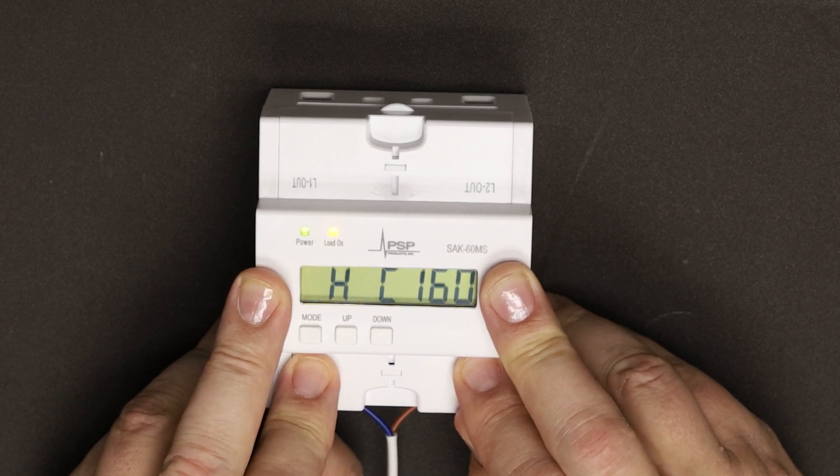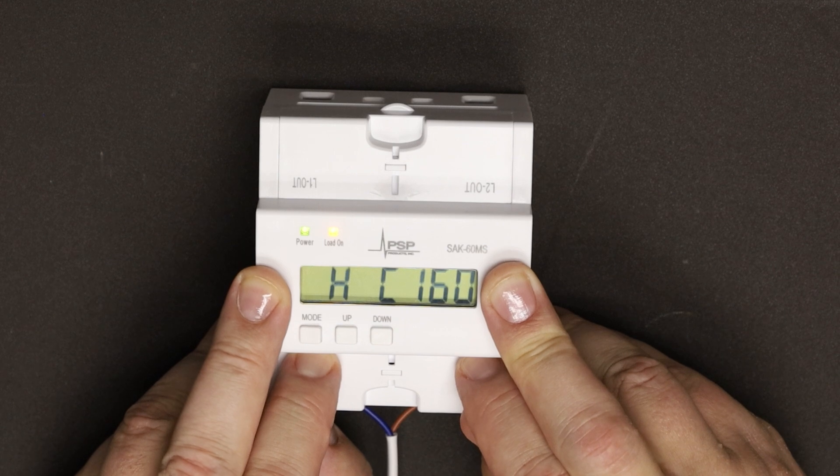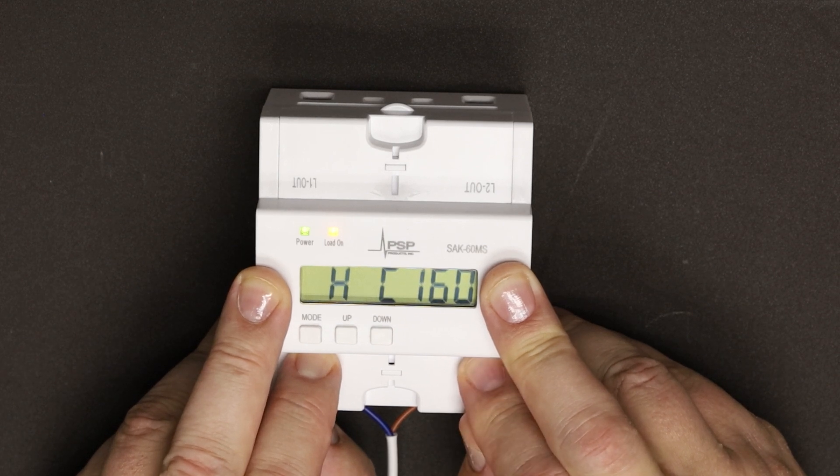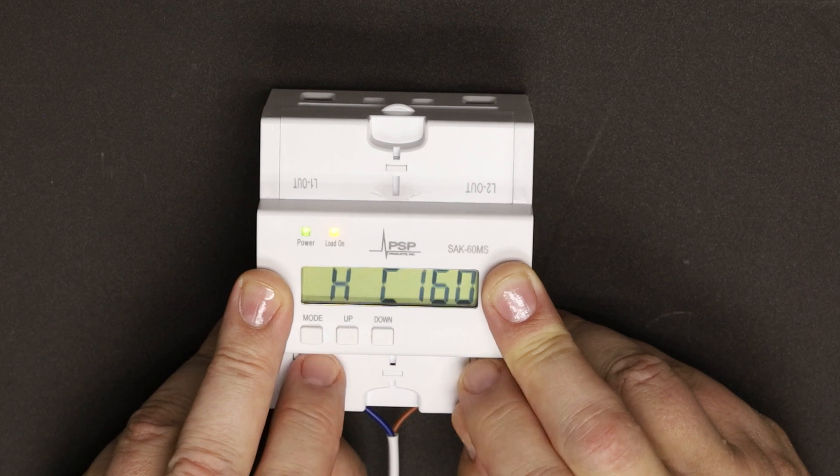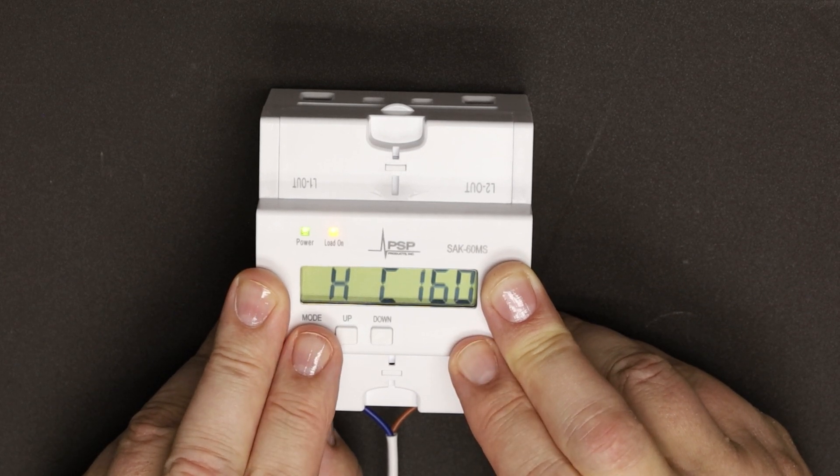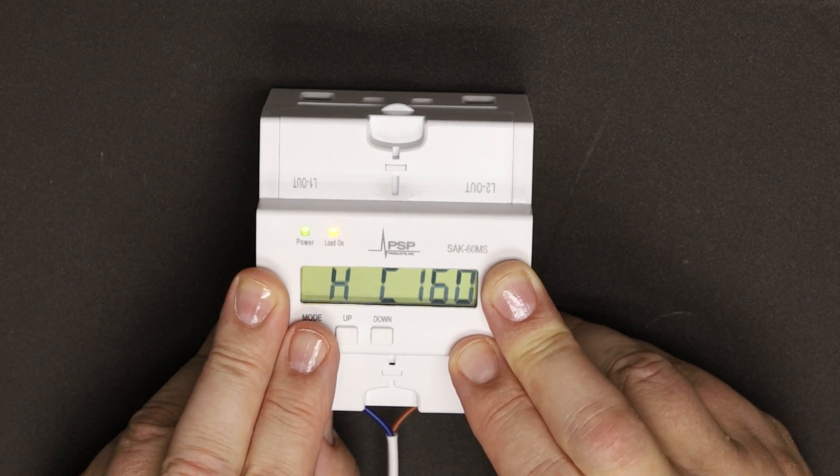HC is the high current set point, or the panel ampacity at which it will drop out the load. I'm assuming a 200-amp panel, and I set HC to 80% of that, or 160 amps.